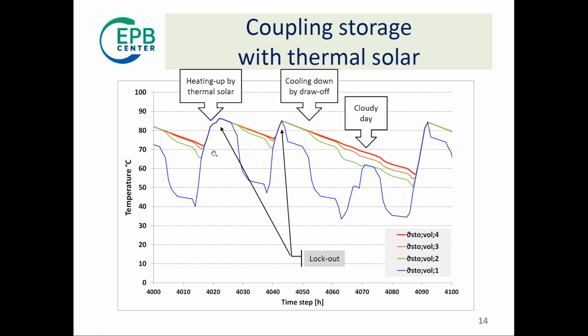You can see this also in the graph of temperatures — these are the 4 temperatures of the 4 layers. Here is the bottom layer with cold water coming in, and in the morning the bottom layer is very cold. It heats up, and then the whole store heats. When you reach this point, you hit lockout because the temperature gets too high, and then it cools down again. Here you have the cloudy day, and nothing happened — everything went well.